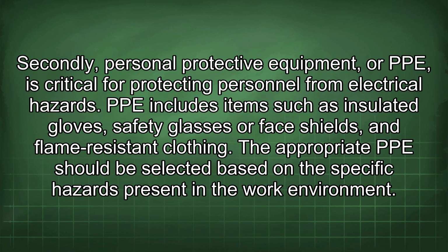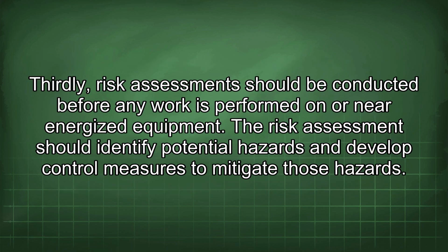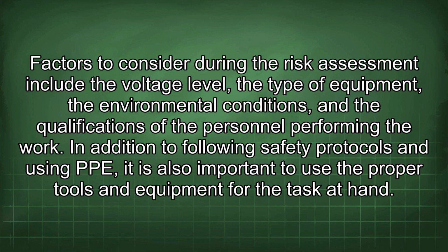Secondly, personal protective equipment, or PPE, is critical for protecting personnel from electrical hazards. PPE includes items such as insulated gloves, safety glasses or face shields, and flame-resistant clothing. The appropriate PPE should be selected based on the specific hazards present in the work environment. Thirdly, risk assessment should be conducted before any work is performed on or near energized equipment. The risk assessment should identify potential hazards and develop control measures to mitigate those hazards. Factors to consider during the risk assessment include the voltage level, the type of equipment, the environmental conditions, and the qualifications of the personnel performing the work.